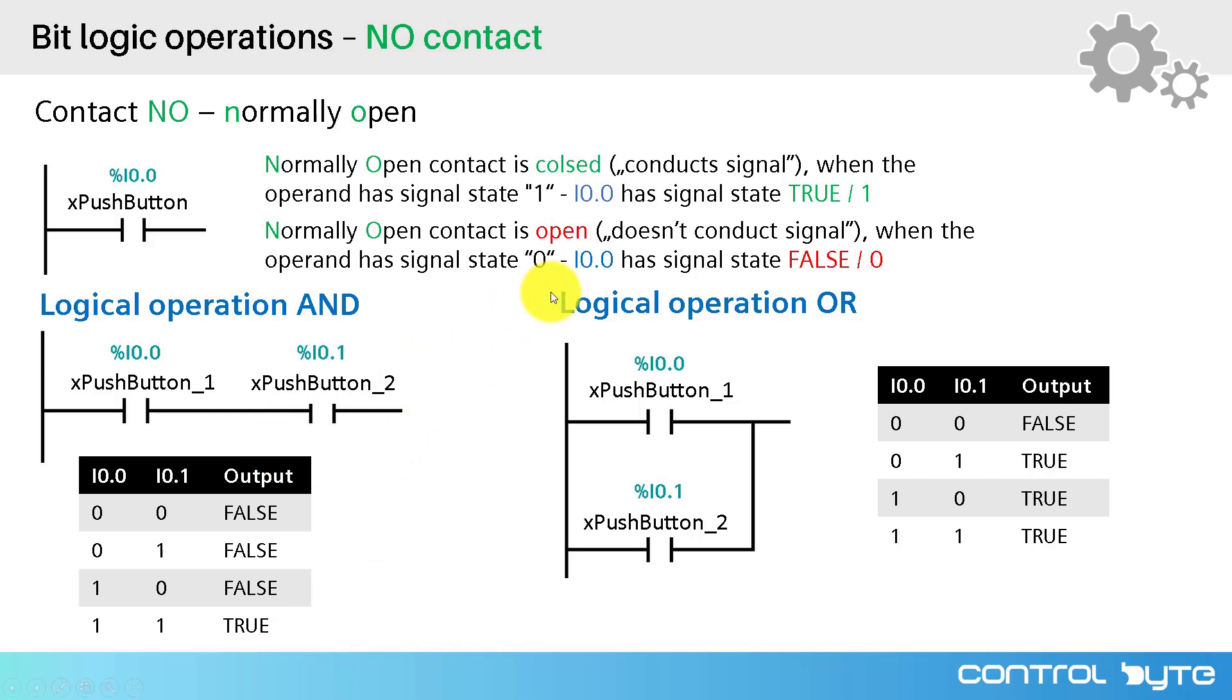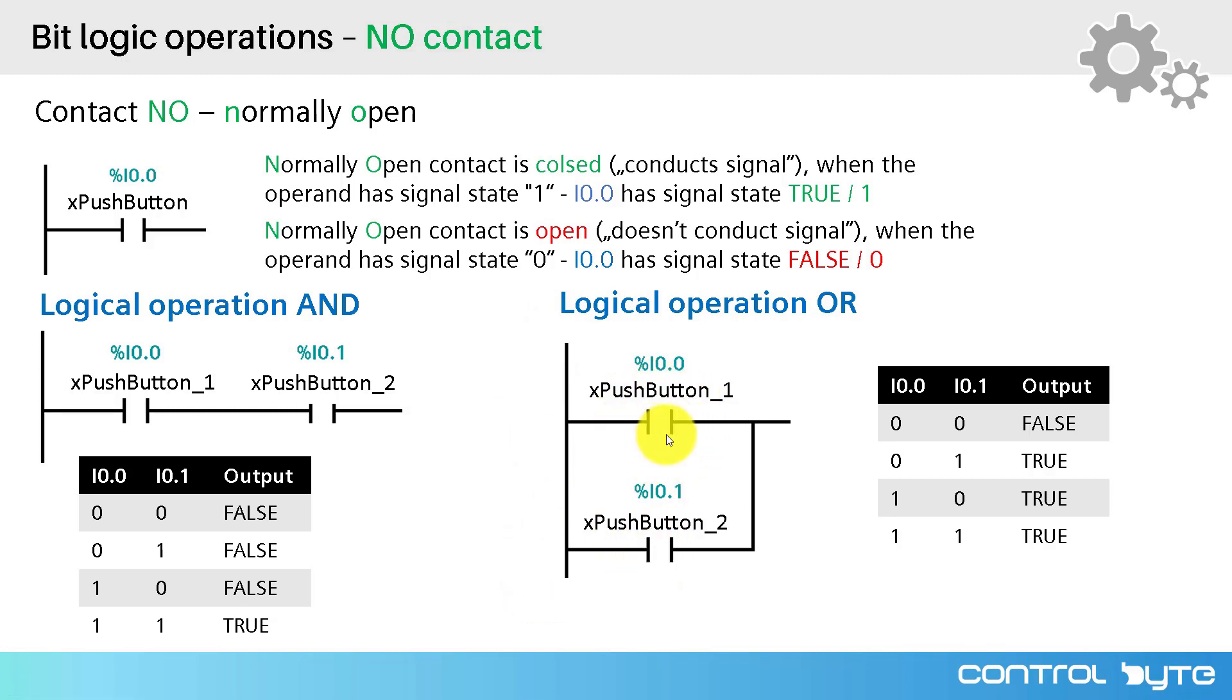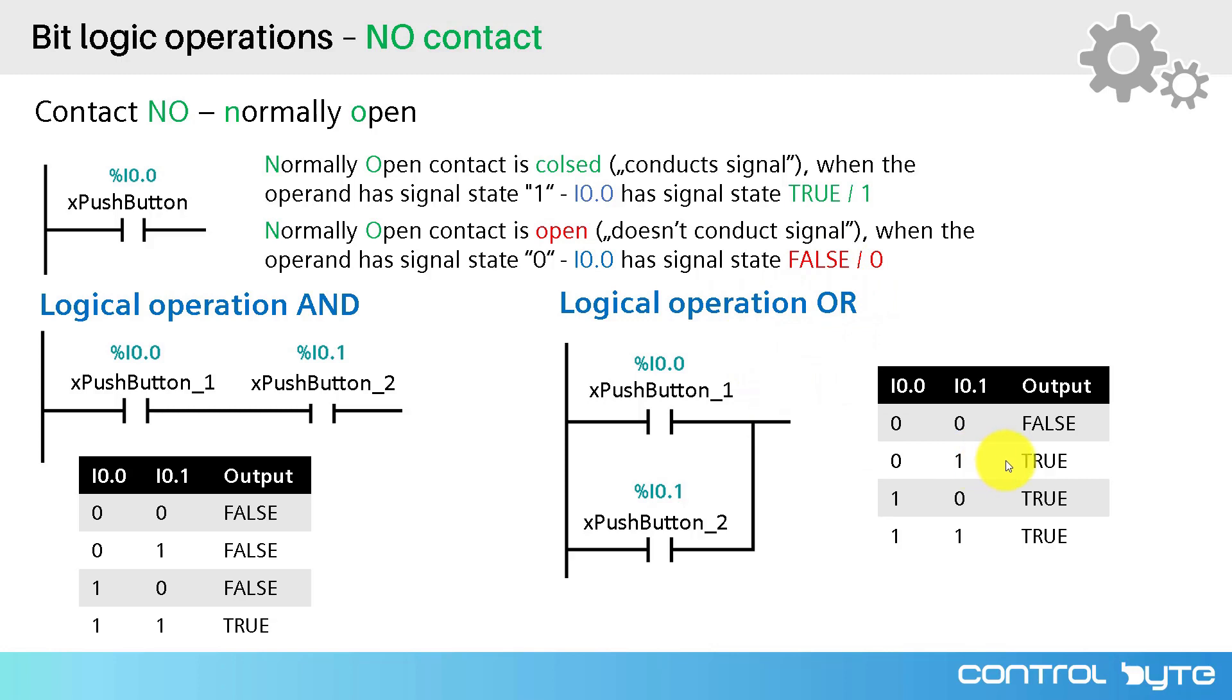Now, let's move on to next logical operation. It is operation OR. To build such an operation in ladder diagram, you have to place two normally open contacts in parallel. On the right you have truth table for this operation. As you can see, in OR operation, the output is true if at least one of the operands is true.